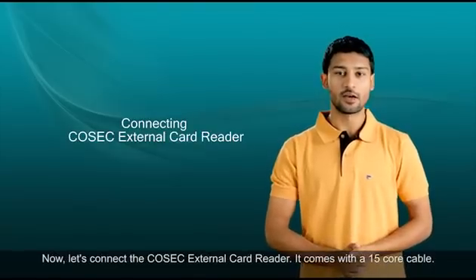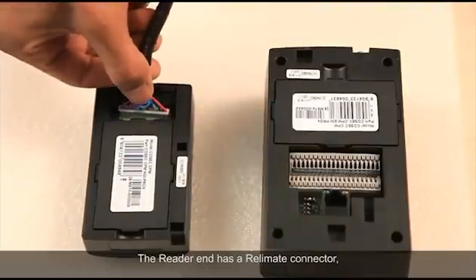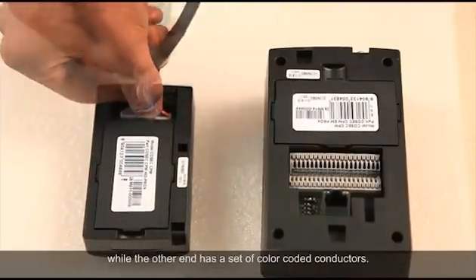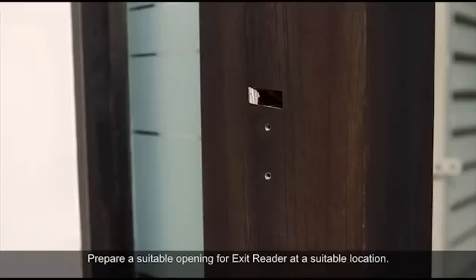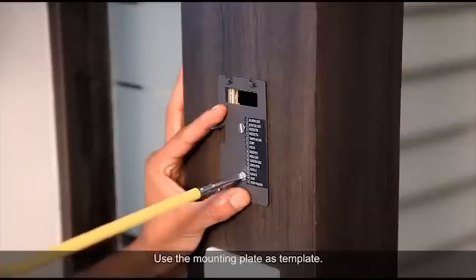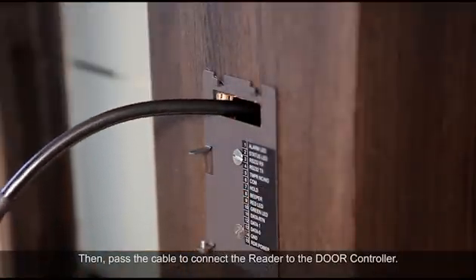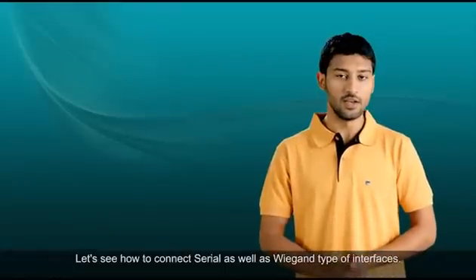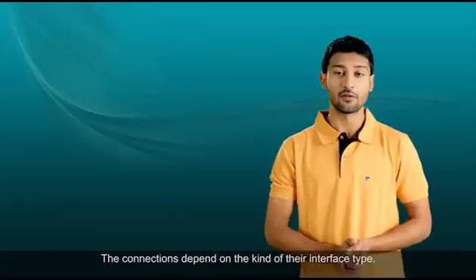Now let's connect the Cosec external card reader. It comes with a 15-core cable. The reader end has a Relimate connector while the other end has a set of color-coded conductors. Prepare a suitable opening for the exit reader at a suitable location, use the mounting plate as a template, and then pass the cables to connect the reader to the door controller. Let's see how to connect both Serial and Wiegand type interfaces.